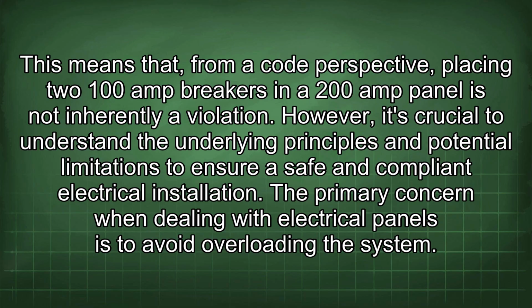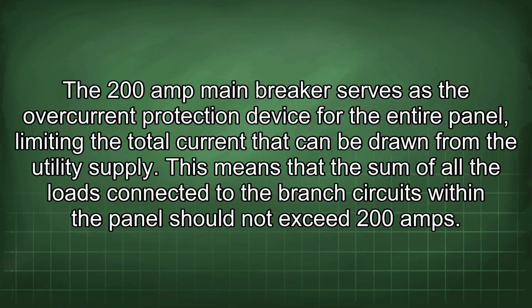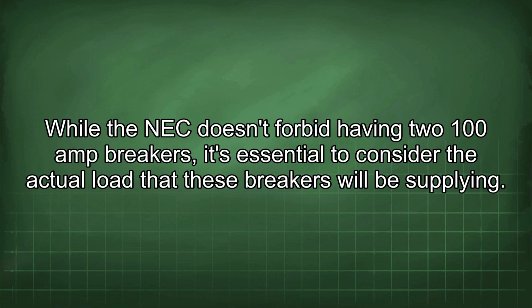The primary concern when dealing with electrical panels is to avoid overloading the system. The 200-amp main breaker serves as the overcurrent protection device for the entire panel, limiting the total current that can be drawn from the utility supply. This means that the sum of all the loads connected to the branch circuits within the panel should not exceed 200 amps.